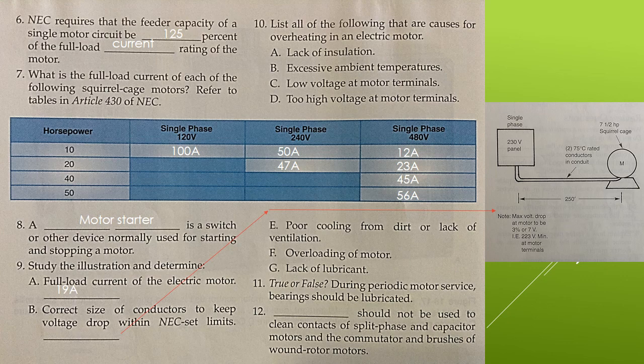Question 8. A motor starter is a switch or other device normally used for starting and stopping a motor. Another answer for that could be a motor controller. Question 9, study the illustration and determine A, the full load current of the electric motor. For a 7.5 horsepower squirrel cage motor, looking at table 430.248, we find that it is a 19 full load amp current motor.